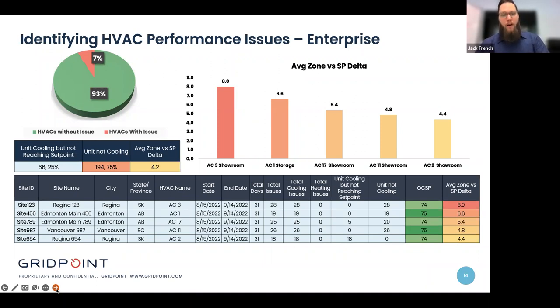So by comparing these each month, and looking at the average zone versus set point delta, you can get an idea of how severe it is, and are we moving in the right direction? If we have rolled trucks and tried to fix these units that we know have consistently had heating issues, did that metric of average zone versus set point delta go down, or is it going up? And of course, it's also important to consider, has the weather been more extreme this month versus last month when we ran this report? Are the same units on this report, or are they all different units?